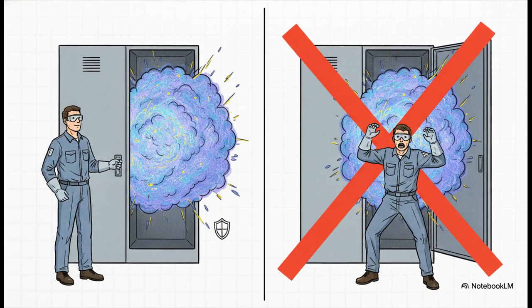Well, the answer is pretty much everything is wrong with this. Bypassing that door interlock instantly removes the arc fault protection guaranteed by IEC 60298. Racking with the door open completely removes your metal firewall. If an arc ignites while you are racking that breaker, which, by the way, is exactly when a mechanical failure is most likely to happen, there is literally nothing between you and thousands of degrees of superheated plasma. Doing this bypass is the single most common way engineers get severely injured or worse.